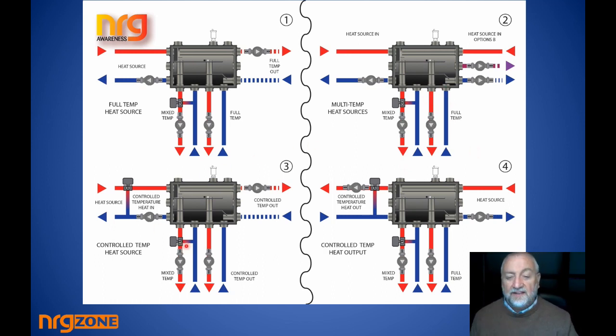In this scenario, we're taking a controlled temperature into the manifold. So for example, if this was coming from another manifold or from something that is a high temperature boiler or whatever, and at the same time we want to mix the temperature down before it gets to zones, we might have, say, 80 degrees over here being mixed down to, say, 50 or 60 degrees here, and then the return is going to be, once the manifold is hot, the return will bypass through this valve and circulate within the chamber, and therefore if you have, say, an underfloor zone, it'll reduce the temperature again, because this is a further step down.